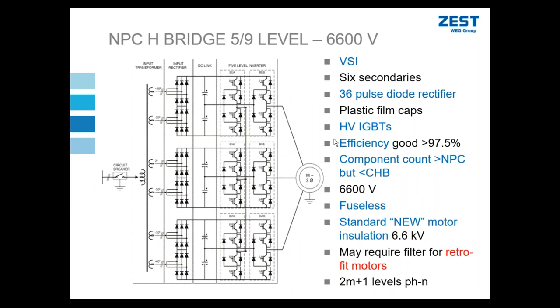Now we discuss the third inverter topology. This is essentially a hybrid between the NPC topology and the H-cell topology that is available for a 6.6 kV application only, cannot go up to 11 kV, but it gives you some benefit of both topologies where you have to have a 6.6 kV output. Here we need only 6 secondary windings, whereas on the typical H-cell, we would need 18 secondary windings. So we're able to reduce the complexity of the transformer somewhat.